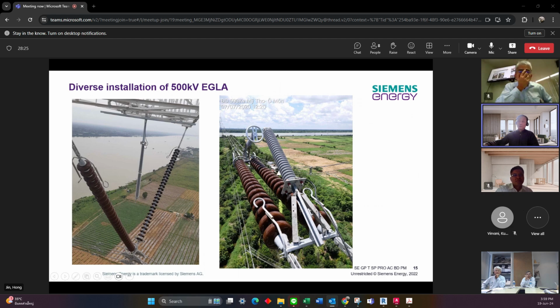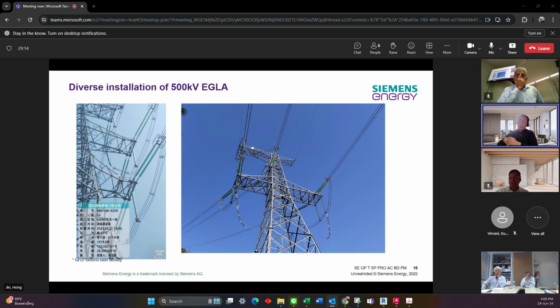If you use it for the V-string, then we have one assembly of the surge arrester. If you use it for the tension string, then we have two different SVU. Two surge arresters will be separated, but the electrical configuration will be the same. Well, as we just read the drawing from Luang Prabang, we will see that in this transmission line, they have even more different transmission towers and also more different insulators. Not only V-string, they also have double suspension, single suspension, double tension and so on. So this is also the question of where we need to install the surge arrester as protection, on which phase, and also how we can now simplify the logistics process, and later also the installation process.